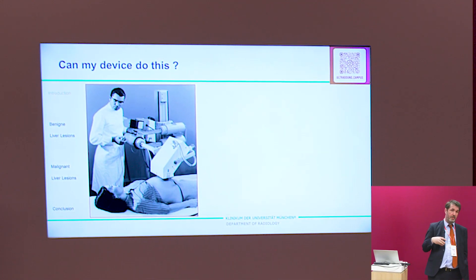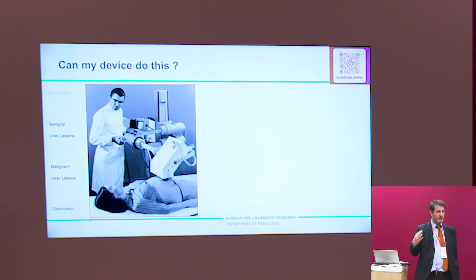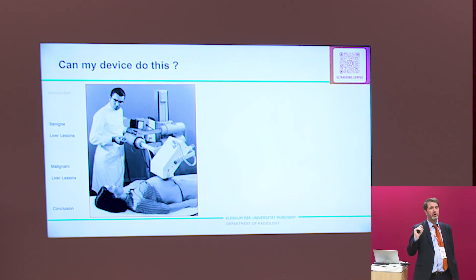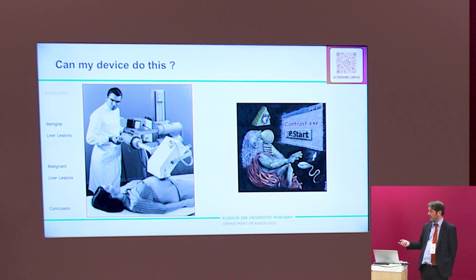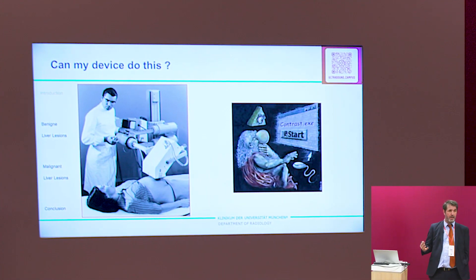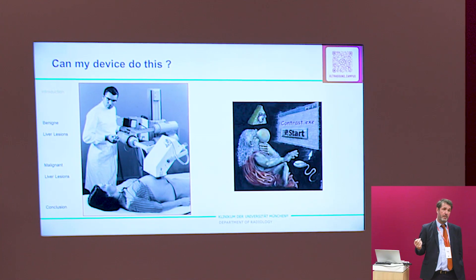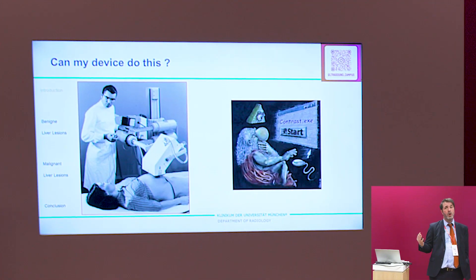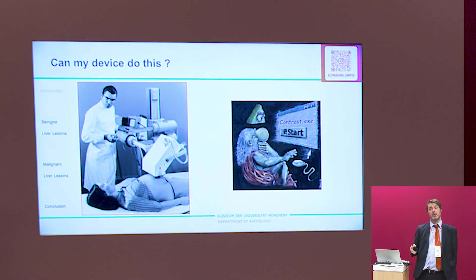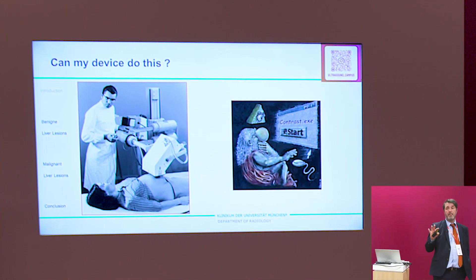This ultrasound equipment is at least 50 years old — even if you inject contrast, you will probably have no success. We need special software, like a Windows PC upgrade. You have to upgrade the system to contrast performance — either bought when you purchased the system, or by checking whether your existing system can be upgraded. Without this software, it makes no sense to start with contrast.